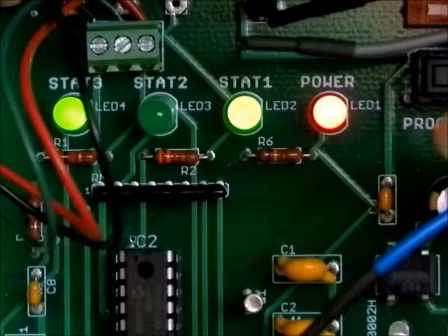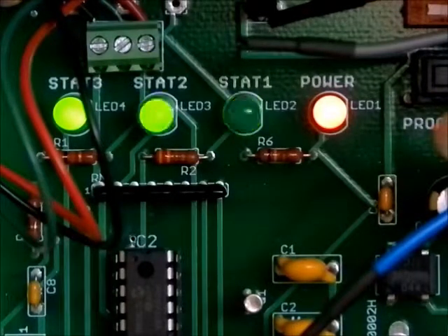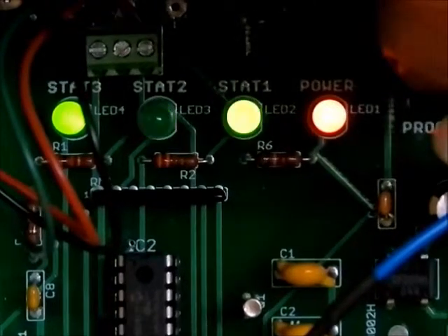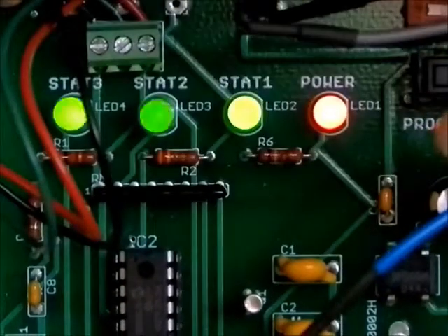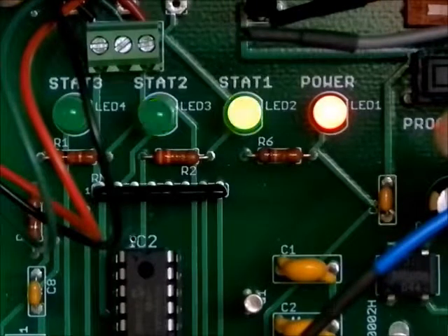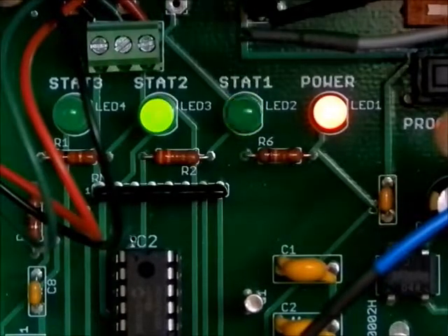If the target machine is still operating at normal speed, STAT3 will turn on solid to indicate that the underspeed signal is now on. To deprogram the underspeed function, we simply press and release the SC1 push button. STAT3 will begin to blink, and after about 5 seconds it will blink rapidly and go out, and the underspeed function is now disabled. This video has shown you the basic operation of the Scorpion SC1 speed switch device.